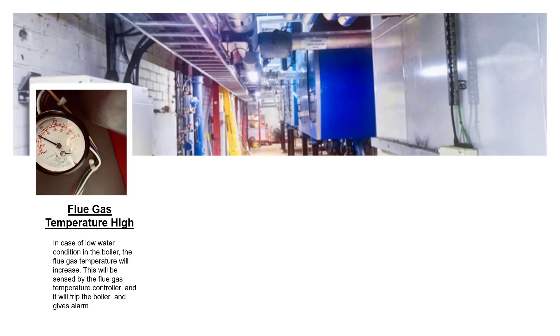Flue gas temperature high: in case of low water conditions in the boiler, the flue gas temperature will increase. This will be sensed by the flue gas temperature controller, which will trip the boiler and give an alarm.